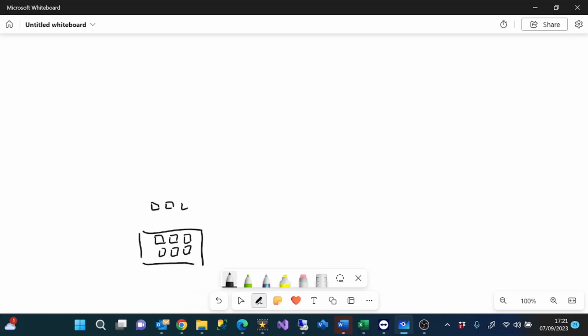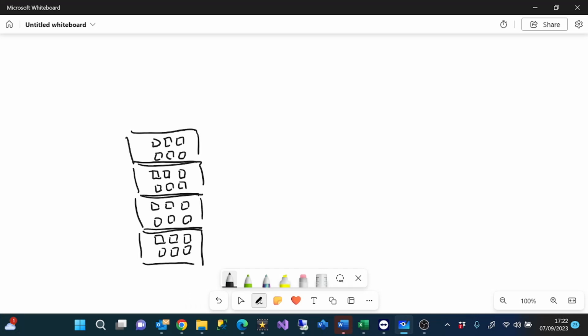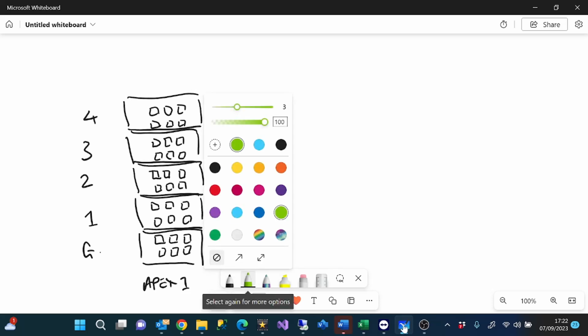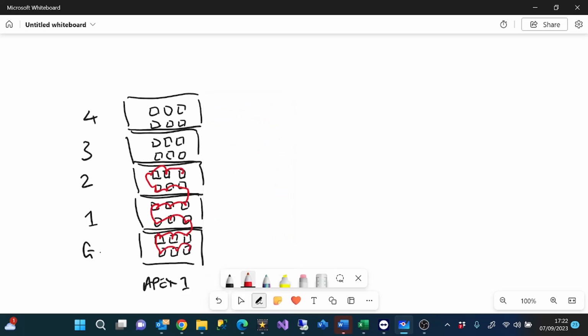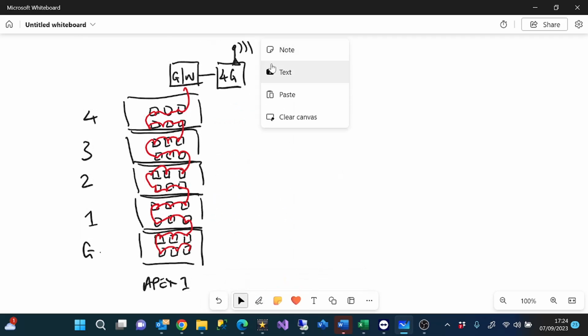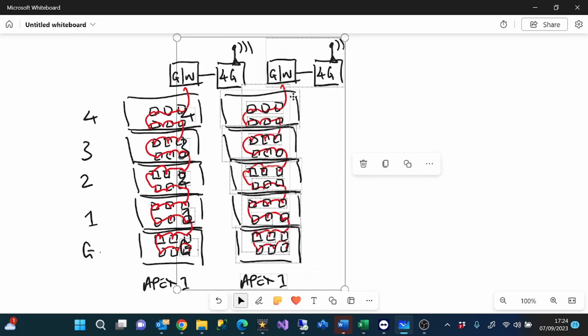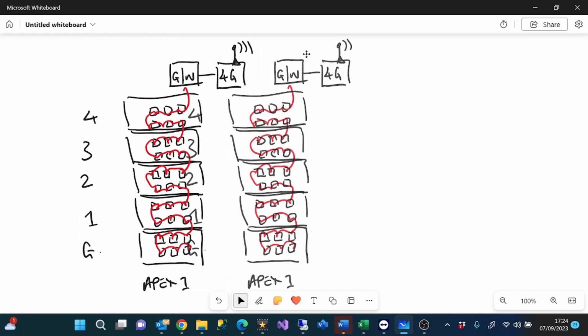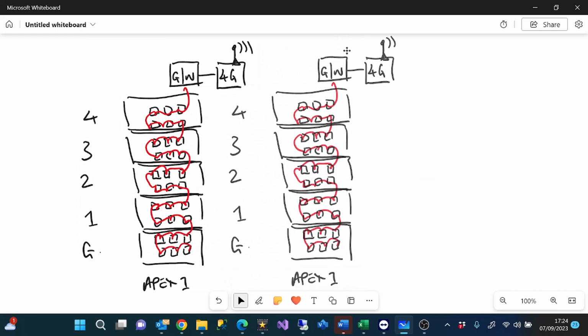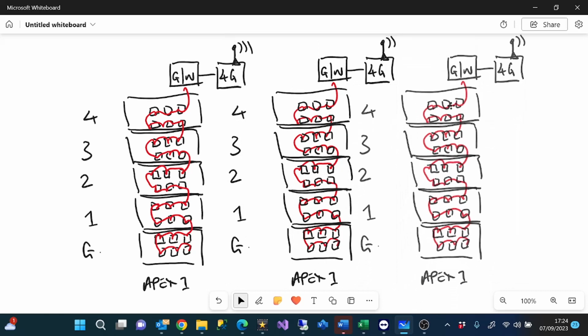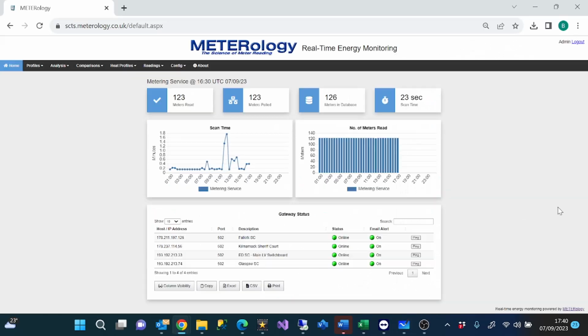A 2-wire Modbus RS485 network cable would then daisy chain between each meter and would route up the riser to the rooftop plant room where a Modbus gateway and a 4G modem would be fitted. This arrangement would be repeated for each building and the data from each meter within each building would be automatically logged every half hour into a central database.